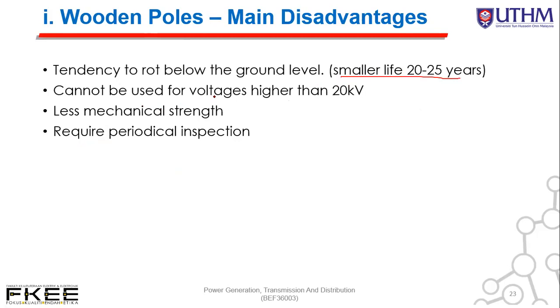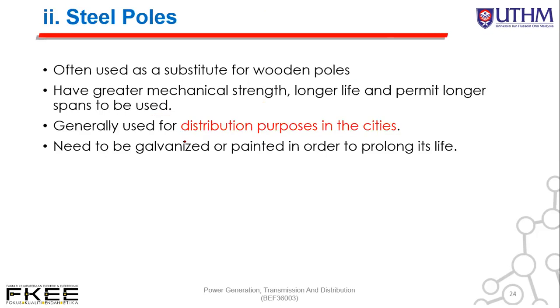Steel poles are often used as a substitute for wooden poles. They have greater mechanical strength, longer life, and permit longer spans to be used. They are generally used for distribution purposes in cities. They need to be galvanized and painted in order to prolong their life and prevent rusting.